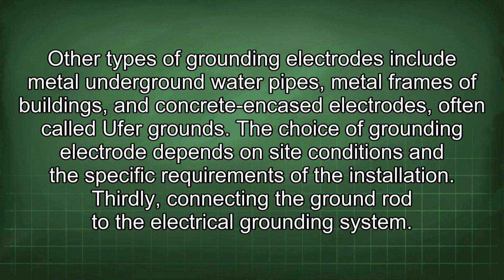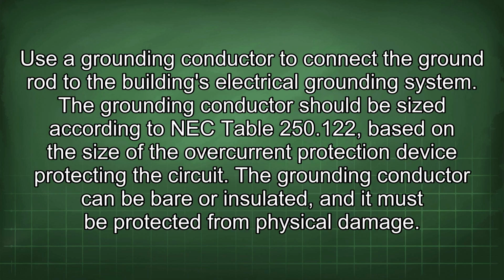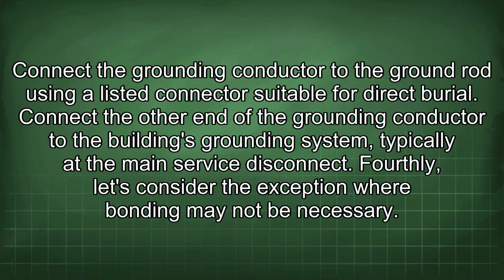Thirdly, connecting the ground rod to the electrical grounding system. Use a grounding conductor to connect the ground rod to the building's electrical grounding system. The grounding conductor should be sized according to NEC Table 250.122, based on the size of the overcurrent protection device protecting the circuit. The grounding conductor can be bare or insulated, and it must be protected from physical damage. Connect the grounding conductor to the ground rod using a listed connector suitable for direct burial. Connect the other end of the grounding conductor to the building's grounding system, typically at the main service disconnect.